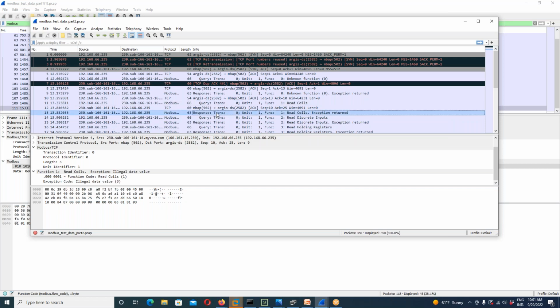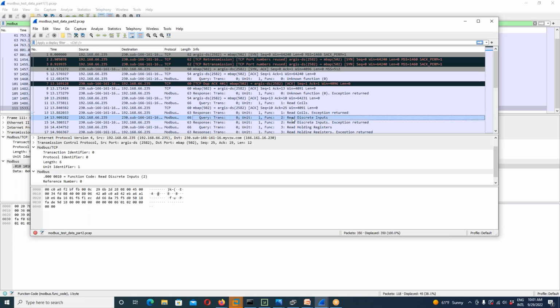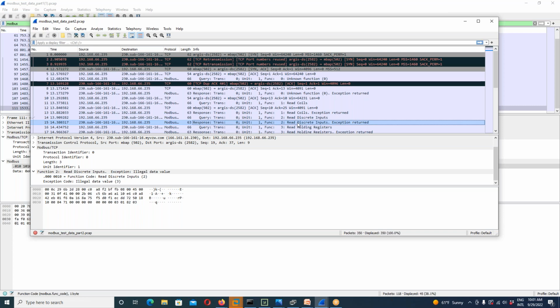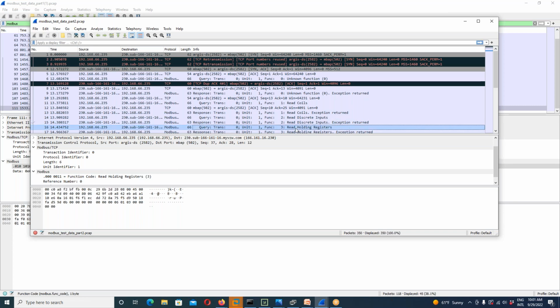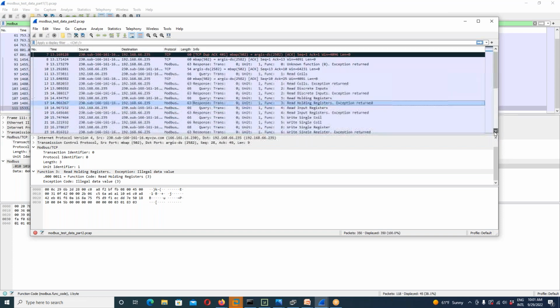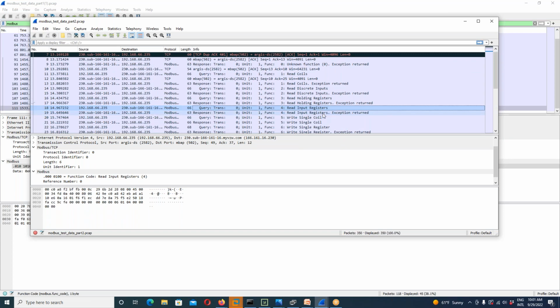More read coils came back with an exception return. There was a problem, looks like it came back with an error message trying to read the coils. Read discrete inputs came back with an exception. Read holding registers came back with an exception. So they're going through trying to find as much information as they can. Read input registers - looks like each one of them failed.